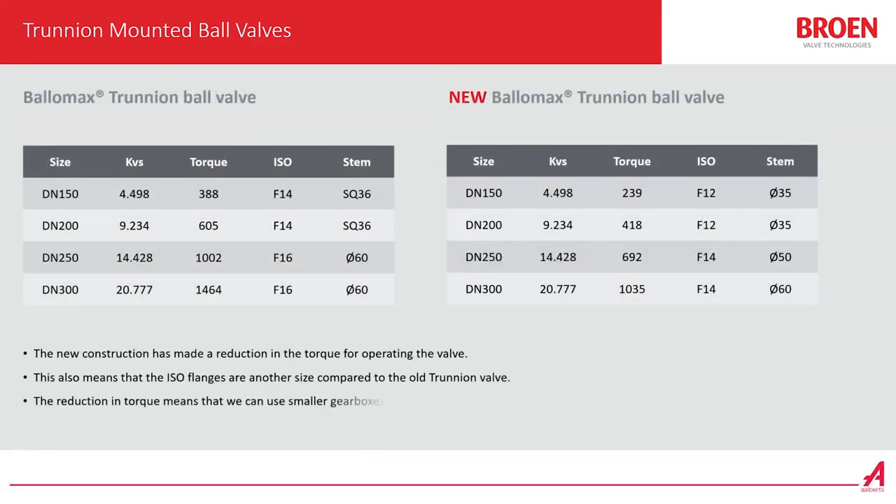Here we have two tables showing the torque. The table on the left shows the torque from the previous model, and to the right we have the new Trunnion ball valve torque, which is lower than before. The new value is 239 versus the previous 388, which also means that we go from an ISO flange F14 to an ISO flange F12. This means that we can use a smaller gearbox or actuator.